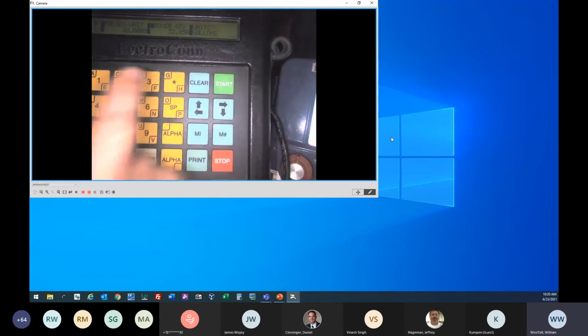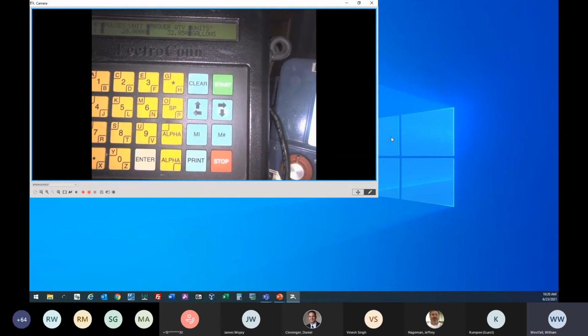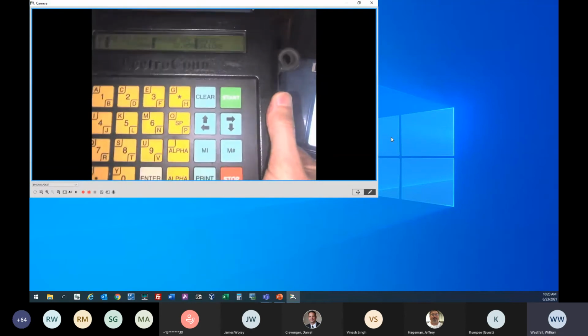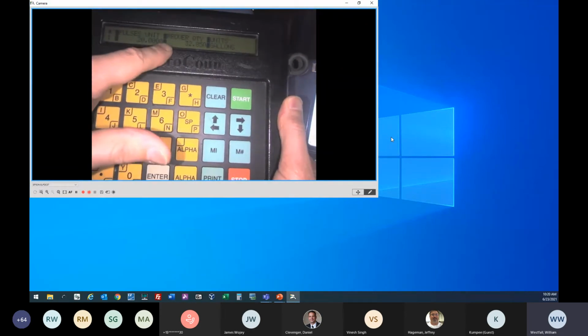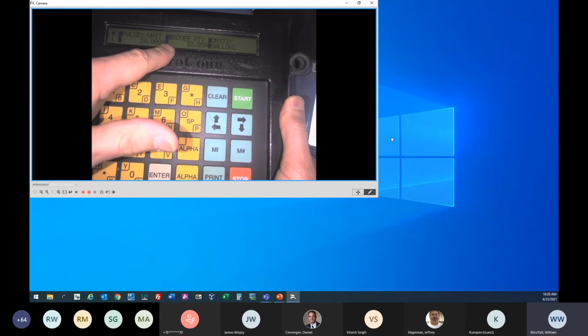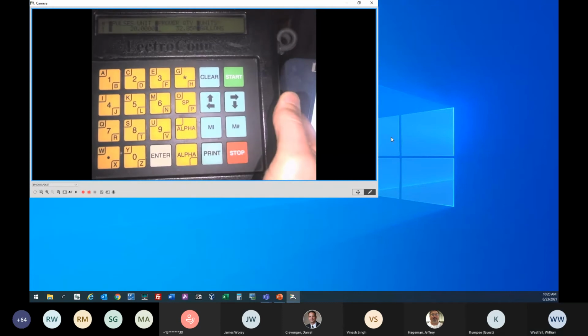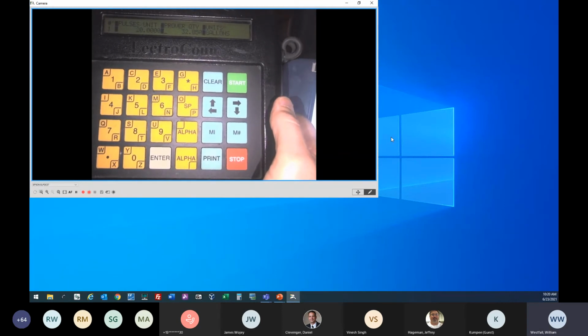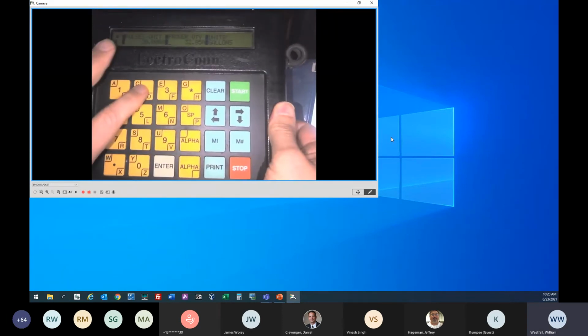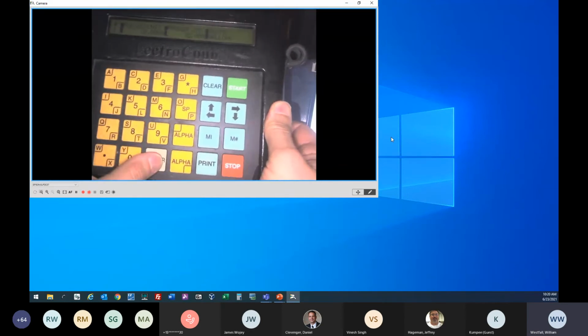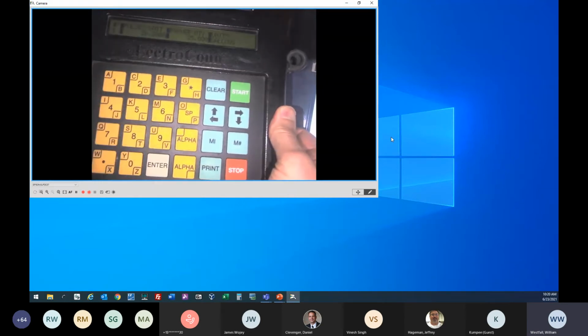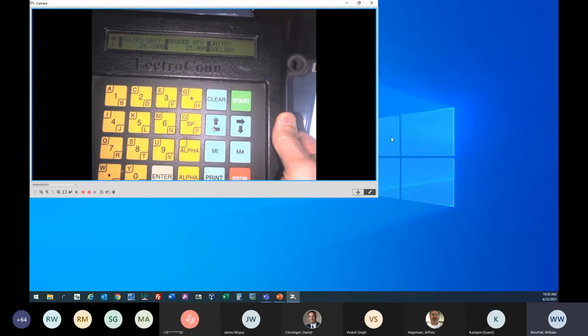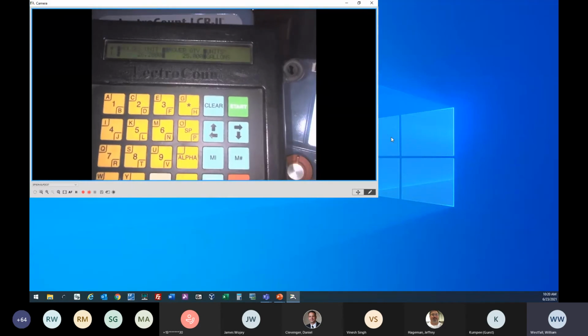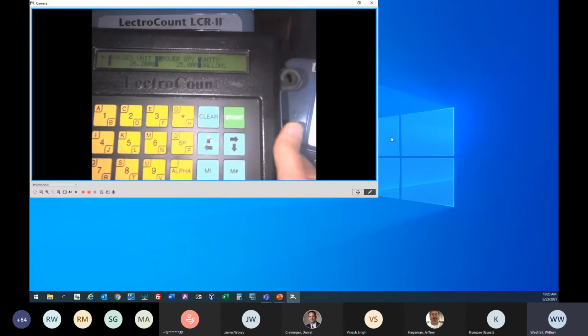Then we want to arrow over to the prover quantity. One thing about using a keypad: when you're using the keypad to enter information, we have to make sure that we're getting a flashing cursor here. This allows us to drop down by hitting the enter key, so that we can actually enter the information. So let's say we had a 25-gallon prover, and we hit enter. Now you can see our pulses per unit changed by itself there. By putting in that prover quantity, it changes your pulses per unit.